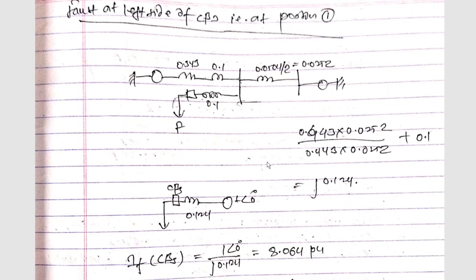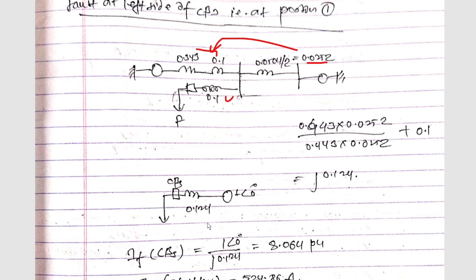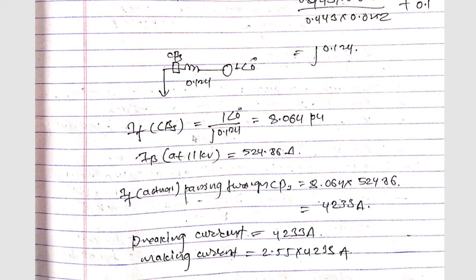With G2 omitted, we have 0.343 + 0.1 in series on the G1 branch. This series combination is in parallel with 0.0252, and that result is in series with 0.1, giving j0.124 overall. The fault current through circuit breaker 3 = 1 / j0.124 = 8.064 per unit. The base current at 11 kV = 524.86 ampere, so actual fault current = 8.064 × 524.86 = 4233 ampere.